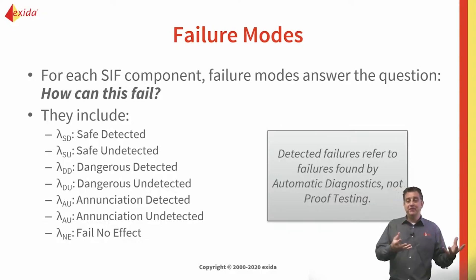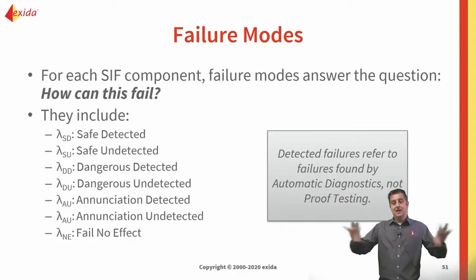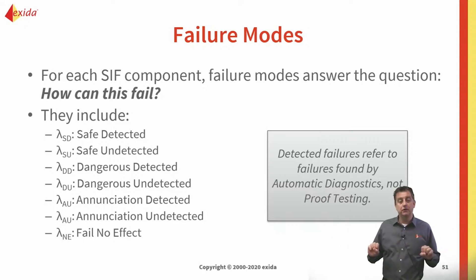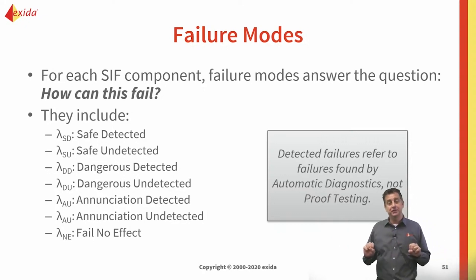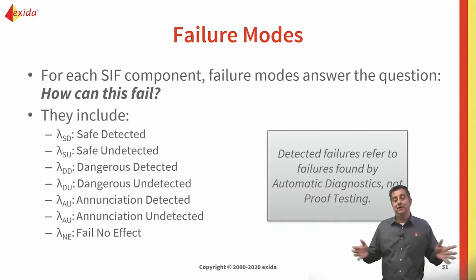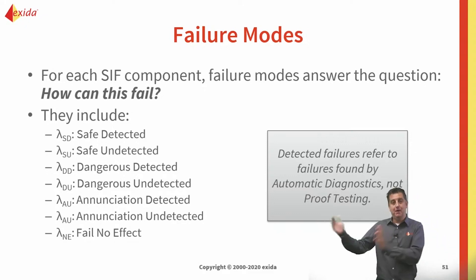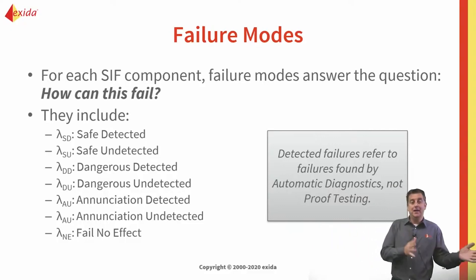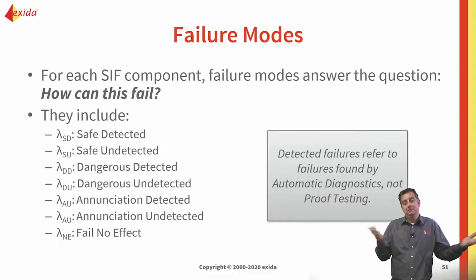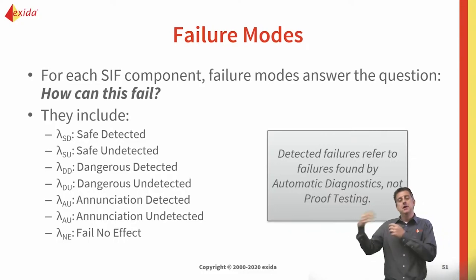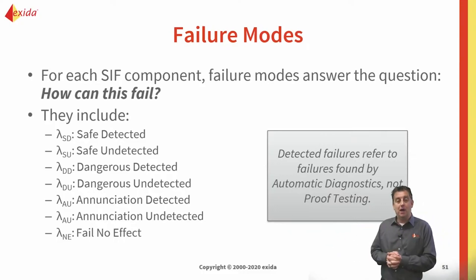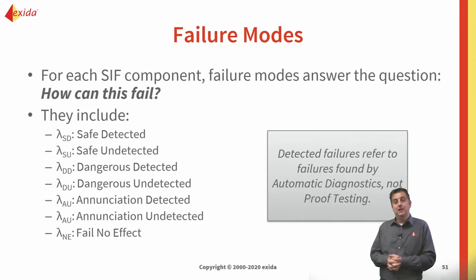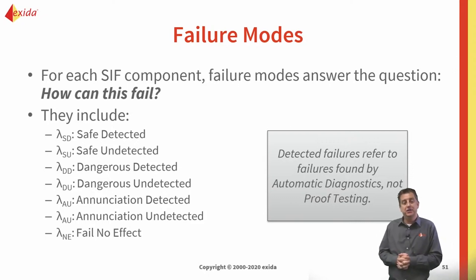In a single non-redundant system, safe detected and safe undetected failures will both produce the same output — the output goes to the safe state. In one case you know a failure caused it; in the other you won't immediately know the cause and will need to investigate. In both cases, the output is the same.